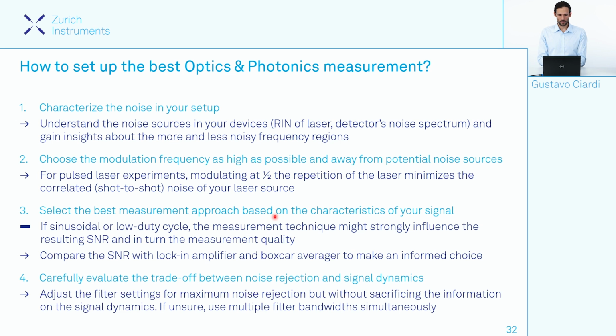Then we always need to evaluate and assess the trade-off between noise rejection and signal dynamics. This means we need to adjust the filter settings to achieve as much noise suppression as possible, while making sure that we are not filtering out relevant information on the dynamics of our signal. If unsure, one should use multiple measurement bandwidths to check which one is better.